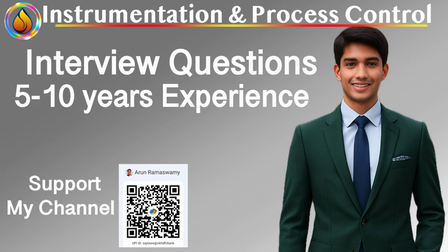What's the difference between BPCS and SIS, and how do they communicate? BPCS, Basic Process Control System; SIS, Safety Instrumented System. Purpose: process control and optimization versus personnel and equipment safety. Availability: highest. Fail state: safe or steady state, always fail safe. Communication: OPC or Modbus read-only from SIS, one-way data flow to DCS. Physical and functional separation is a must. Interaction occurs only via secure gateways.